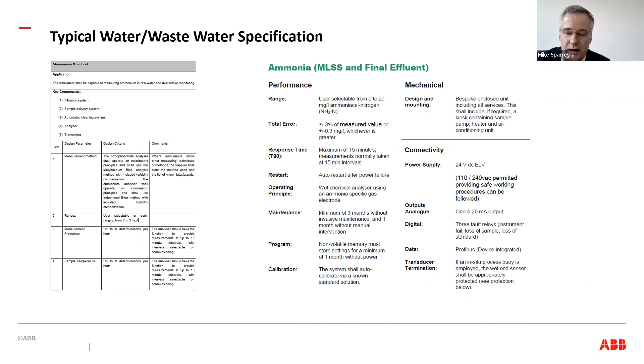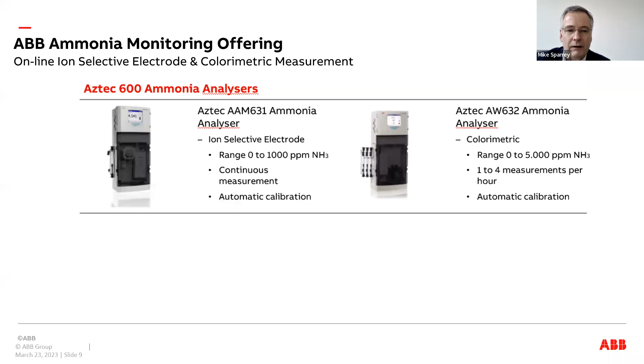ABB has been operating these two ammonia monitors within industry for about a decade. On the left-hand side is our ion selective electrode, with a typical dynamic range of 0 to 1,000 ppm of ammonia, key for industrial markets where levels are typically 3 to 4,500 ppm, and for the wastewater side. Then we have the colorimetric analyzer for the low level side, around 0 to 5 ppm. So depending on the concentration levels, we have to change the technology we use.